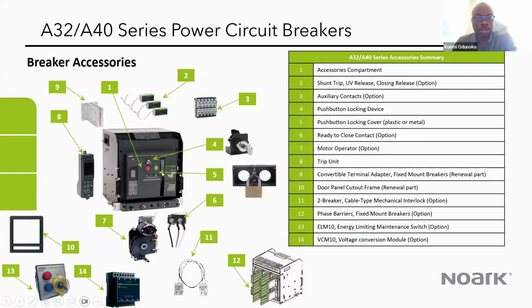Then the motor operator, like we said, helps you to charge the spring, the stored energy spring of the breaker. More importantly is the trip unit. The trip unit is what helps with the protection function that we talked about earlier on. So I'm going to talk a little bit about that in the subsequent slides. I'm just going to run through quickly.